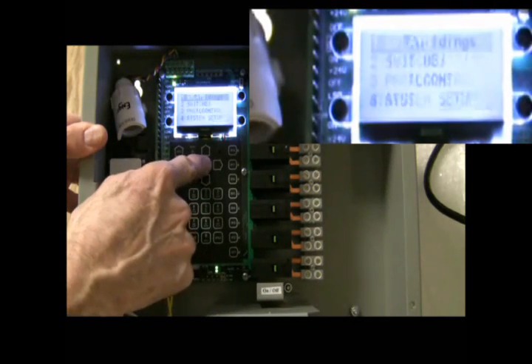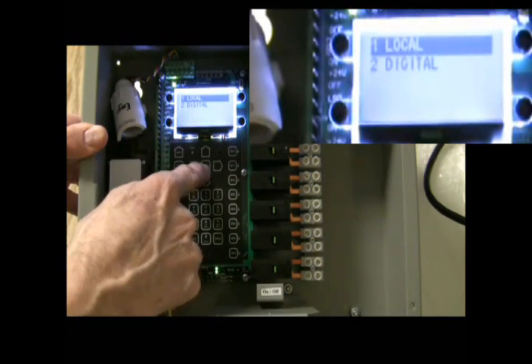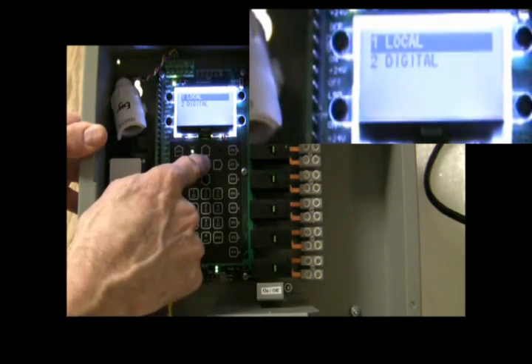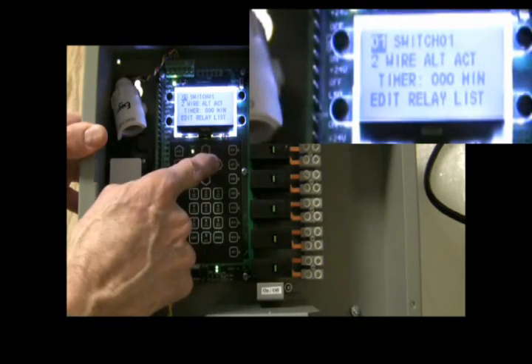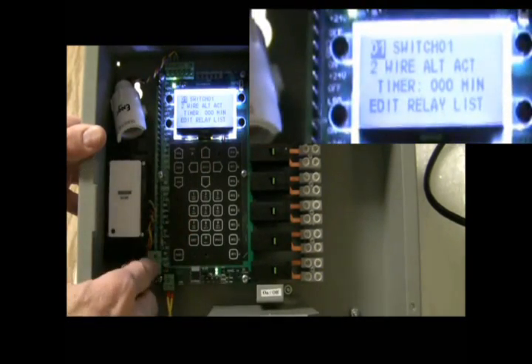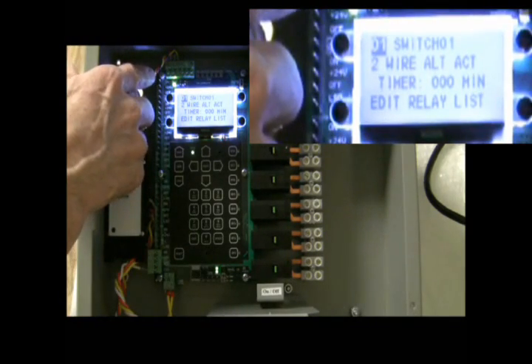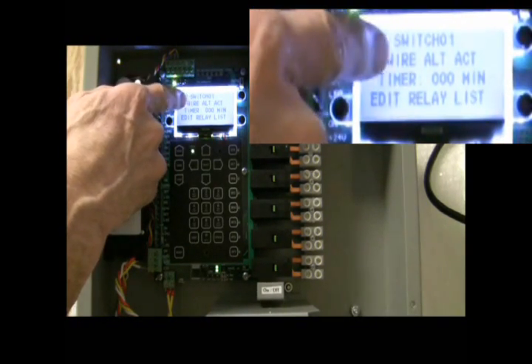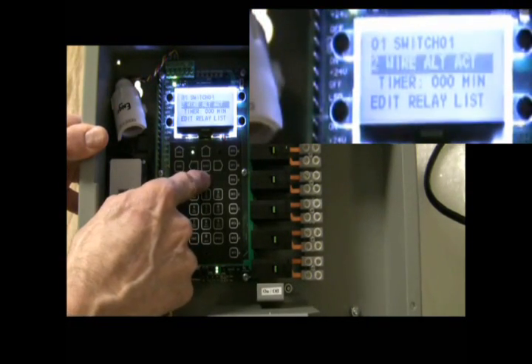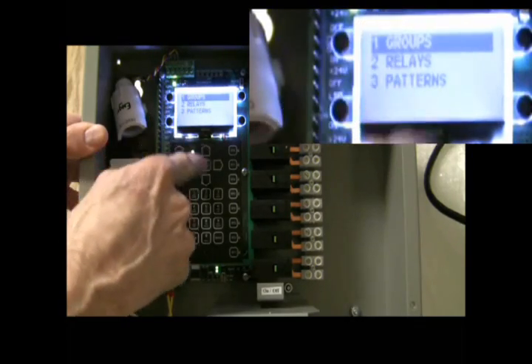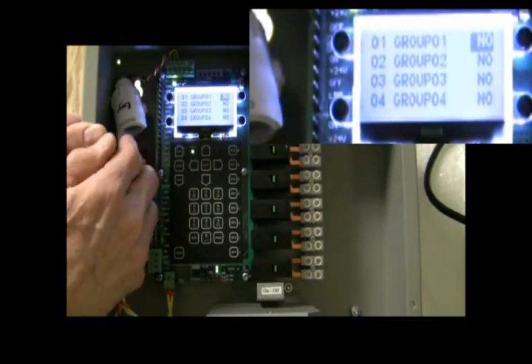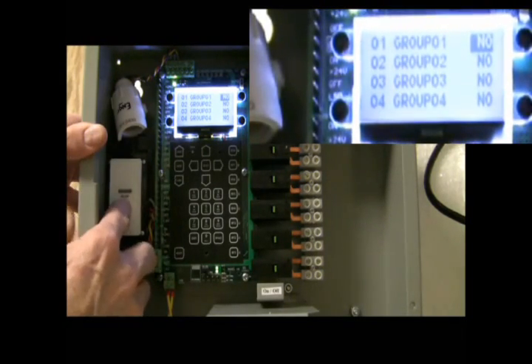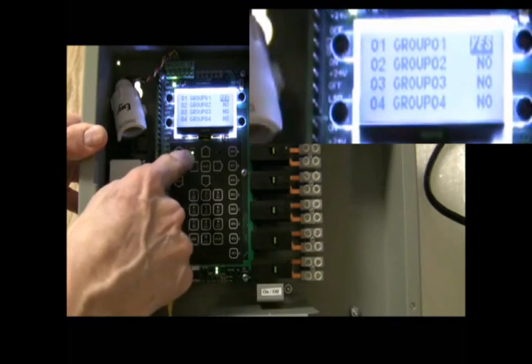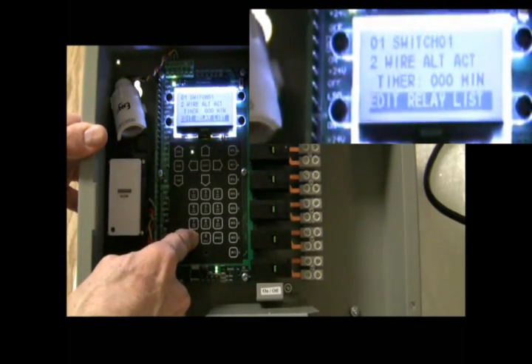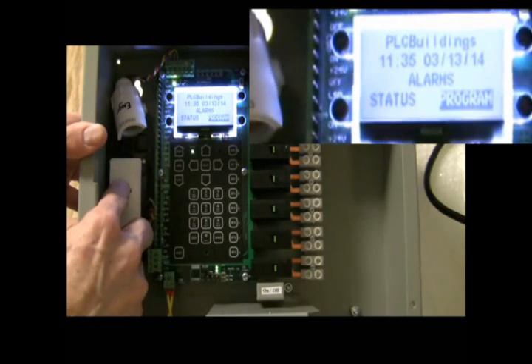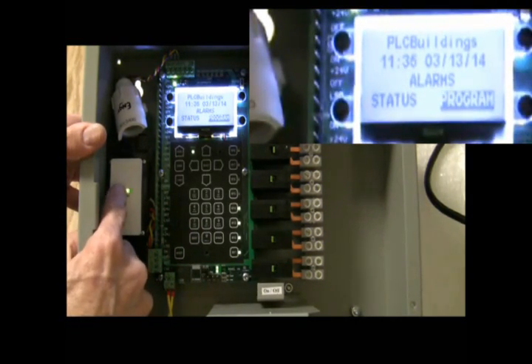Back to switches, program, you can press 2 for switches, local, because it's a local switch, it's not a digital switch. Out of the box, it sets up default, first position is here, 8th position is here, so we're switch 1, it's to our alternate. In order to select the group, you have to say edit relay list, press select, groups. Group 1 is defaulted no. We want group 1 to be affected by this switch 1. So we raise it to yes, save it, exit out. And now the switches will operate group 1.